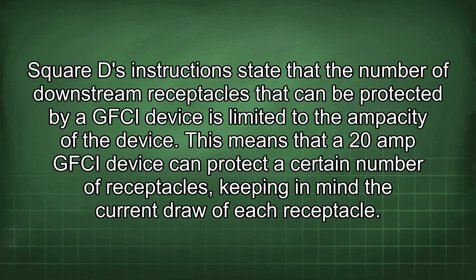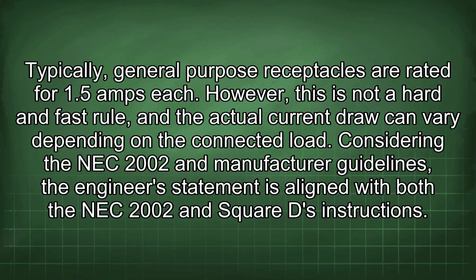This means that a 20 amp GFCI device can protect a certain number of receptacles, keeping in mind the current draw of each receptacle. Typically, general-purpose receptacles are rated for 1.5 amps each. However, this is not a hard and fast rule, and the actual current draw can vary depending on the connected load. Considering the NEC 2002 and manufacturer guidelines, the engineer's statement is aligned with both the NEC 2002 and Square D's instructions.